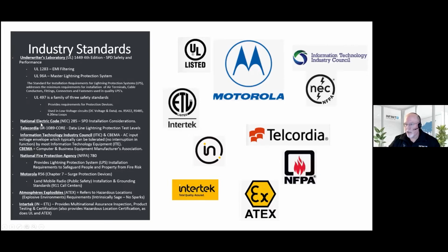The National Electric Code is very critical. That is the standard for grounding, along with the National Fire Protection Association code here. And Motorola R56, they wrote their own standard for installation and grounding for 911 call center type facilities. And Transtector actually helped them develop their Chapter 7 on surge protectors. And they're very, very strict. In addition to where the surge arrestor will be installed, R56 Chapter 7 also tells you not only where, but what technologies to use. And in addition to that, thou shalt just use normal mode protectors.